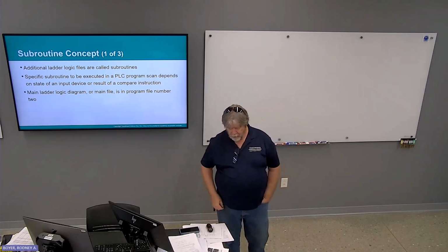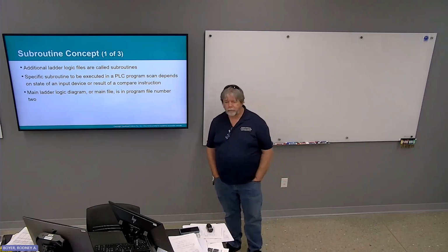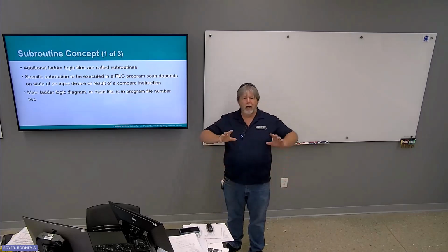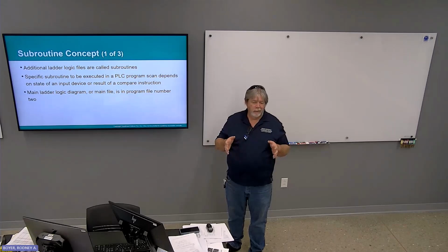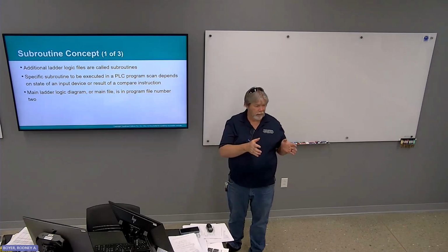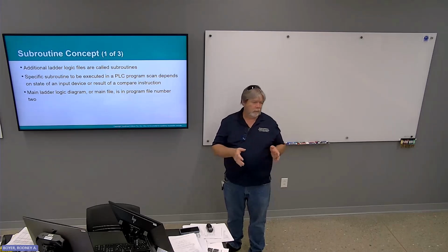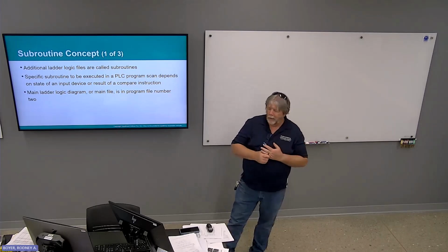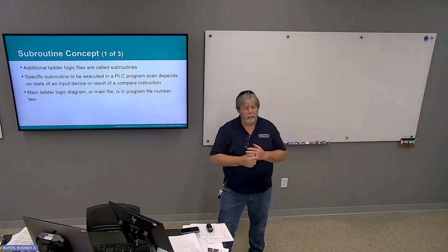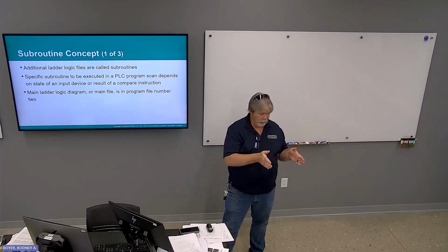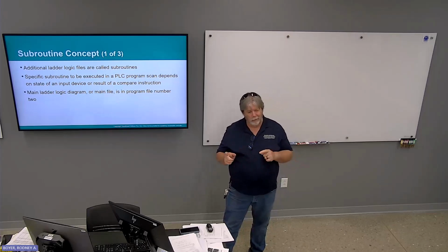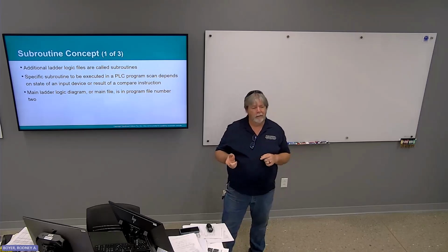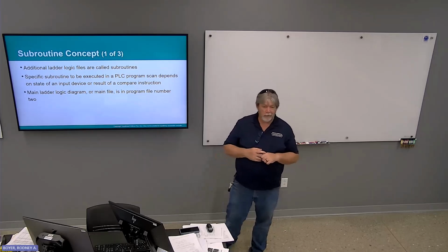If you wish, in order to break your logic up into smaller, logical chunks that make more sense, like a manual routine, a fault routine, an automatic routine, that kind of thing. Those are pretty typical. Some people put the real world outputs in their own output file, and then in the logic you set internal bits, B3 bits, and then those bits are what actually turn on and off the physical I/O in the subroutine file.